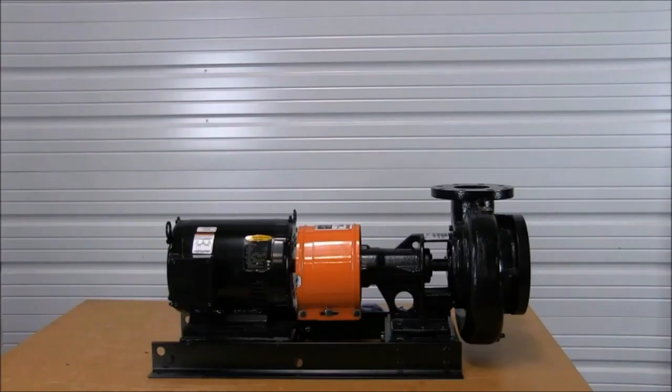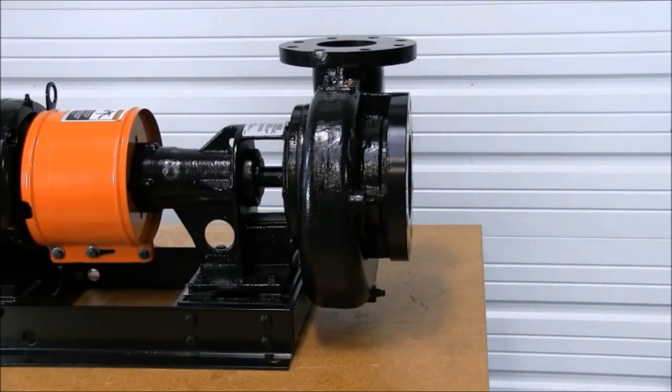This is the Grundfos LF long coupled pump complete with base, motor, pump, and couplings. Before we begin, make sure all power has been locked out to the motor. Once power has been locked out to the motor, close the discharge and suction valves to the pump.